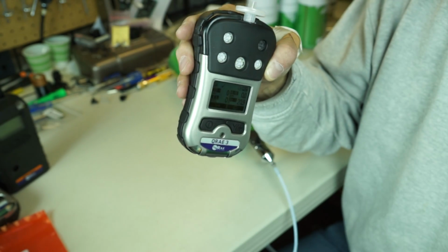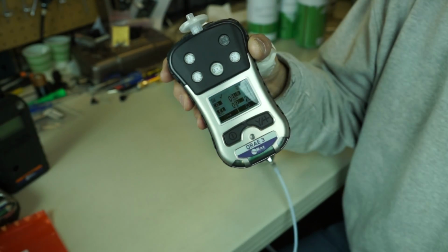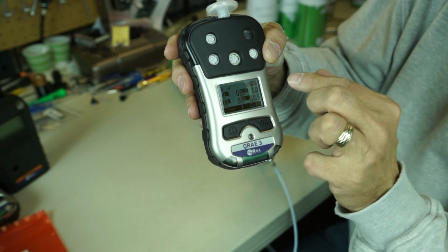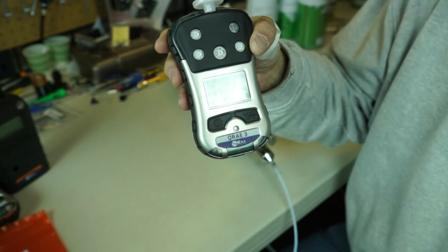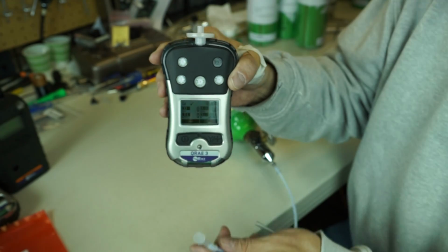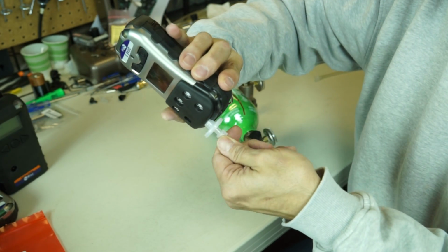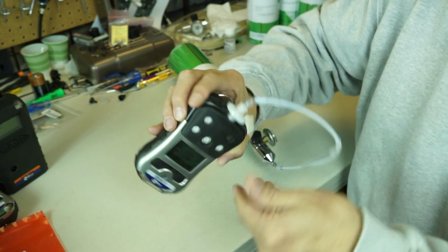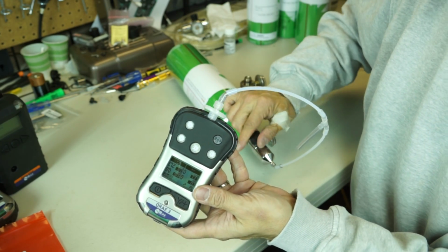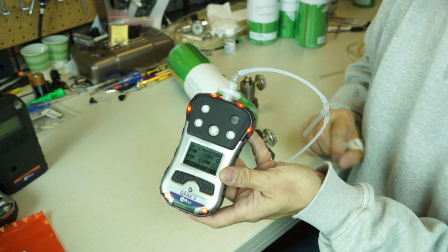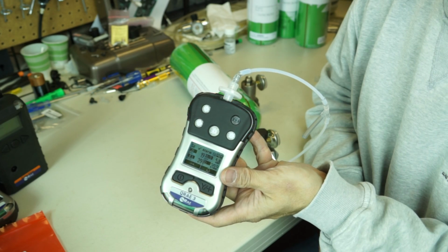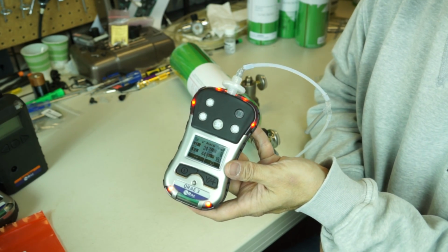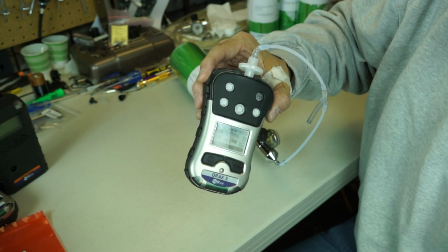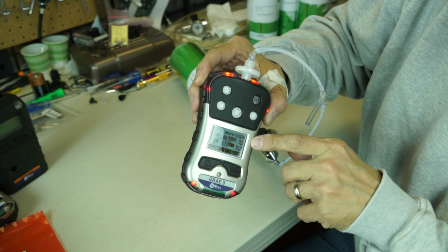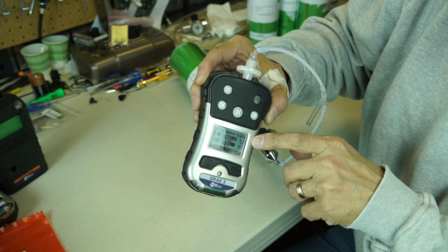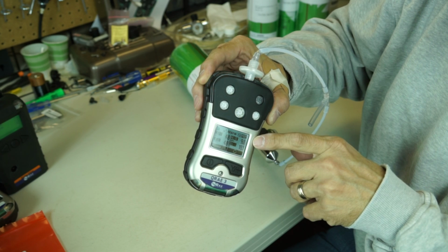Instrument's been fully calibrated. 000 20.9. If you'd like, you can reconnect up to the gas. I like to do this. It's called post bumping. Turn the gas on. Start counting. 1,000, 2, 3, 4, 5, 6, 7, 8, 9, 10, 11, 12, 13, 14.